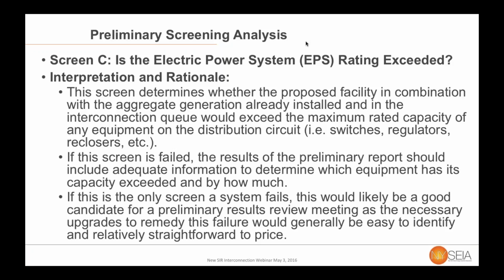Because if you otherwise pass all of the screens that we're talking about, but you exceed the rating for one or two minor pieces of equipment, it may very well be to your benefit to have the meeting. You can agree to the upgrades, and then there are process and timelines within the SIR that the utility can provide you a cost estimate for those upgrades, and then you can choose whether to accept those upgrades or not as a result of your meeting. So this is one of those examples where that preliminary results meeting might be very useful.